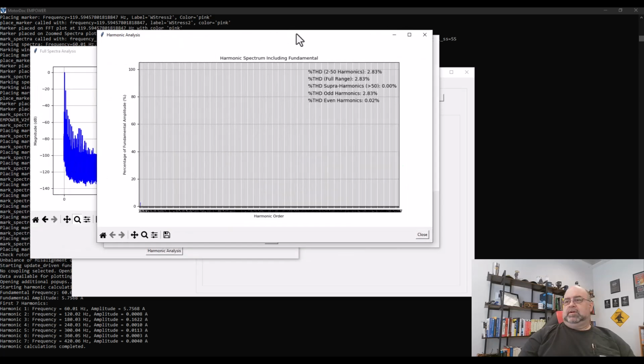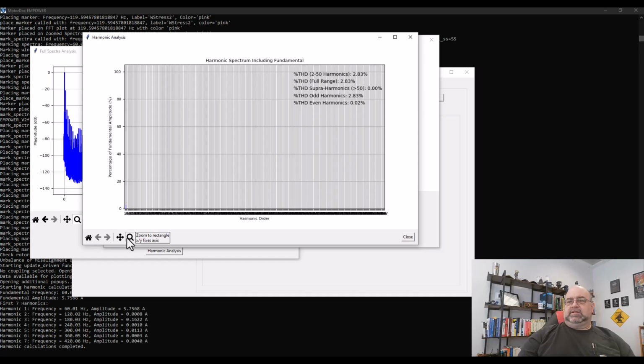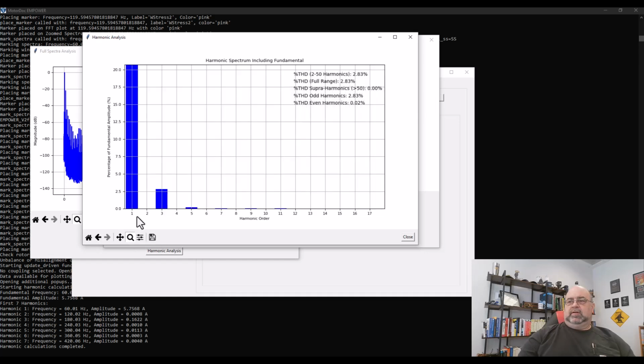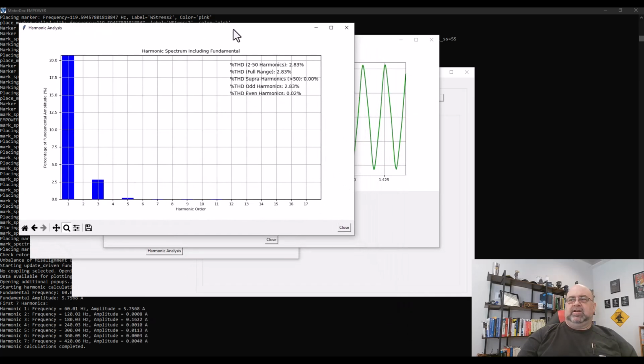Here we go. That's interesting. Let's take a quick look down here. So I have some pretty good third harmonic, about 2.5%. Now, I shouldn't say horrible at all. Teeny bits of fifth and seventh down there. How about that? So 2.83% total harmonic distortion in odd. Really nothing super harmonics, which we didn't see. We would have seen back there under that.